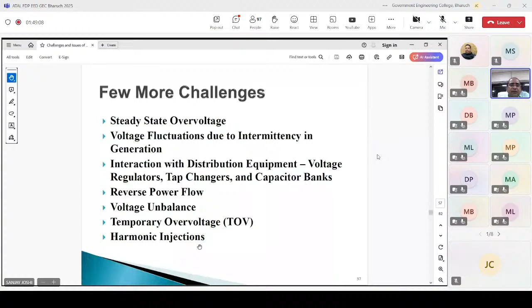Then, because these are all power electronic converters, harmonic injection has also become a problem, because the level of harmonic injection is very huge. Then variability of power output is also a challenge. Protection and control, short circuit current contributions. So fault level, that study is to be carried out by the utility companies and the power system operators. They have to carry out short circuit current contribution studies for these IBRs, right?